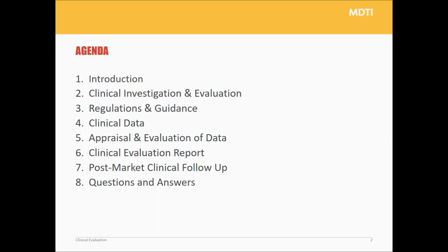And then evaluation, as you'll see, is usually the shortest part of your clinical evaluation. The evaluation itself is more or less a discussion of all the data that you've gathered and appraised. Then we'll just talk a little bit about what goes in a clinical evaluation report. And of course, post-market clinical follow-up is really important.